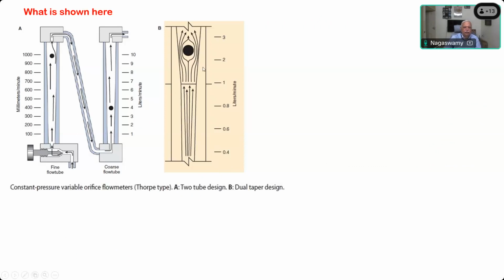Okay. When you have a single tube, as shown in the earlier picture, you can still have flow from point 400 ml, 600 ml, 800 ml, 1000 ml, then 2 liters, 3 liters like that. So this is called the dual taper. Here at the low flow, it is a uniform tapering. Suddenly it becomes very wide. Whereas here, for a low flow, you have a similar type of tube, and then there is a connecting tube in series, then there is a higher flow tube. So this is called the two tube design and the dual taper design.